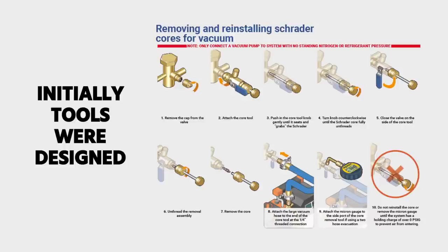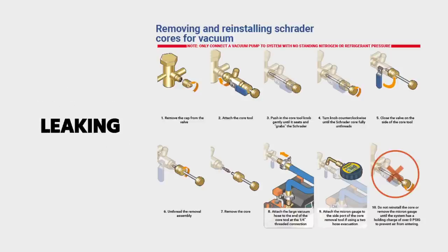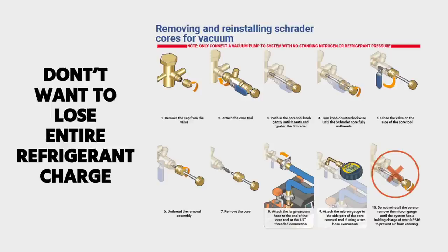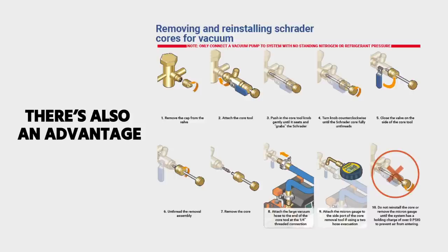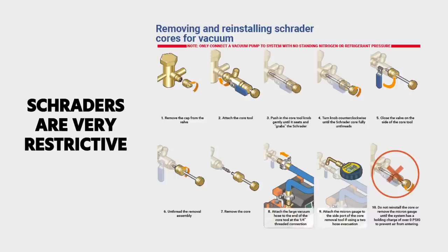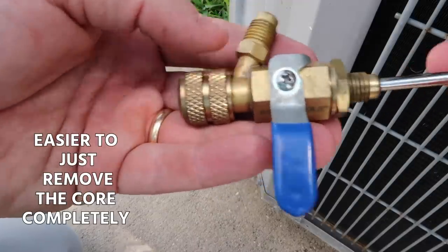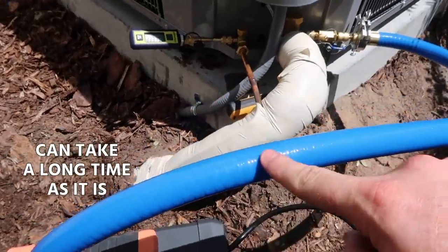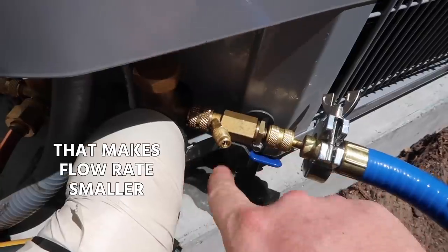Initially, these tools were designed for cases where you had a damaged core that was leaking, maybe overheated or the seal failed for some reason. You want to pull it out but don't want to lose the entire refrigerant charge. But then we realized there's also an advantage because Schraders are very restrictive. To overcome that restriction, it's easier to just remove the core completely before we do things like evacuation or recovery, which can take a long time, let alone when you have a restriction that makes the flow rate smaller.